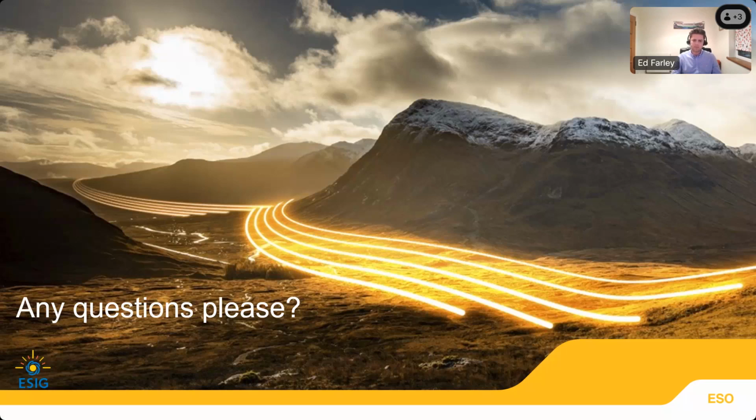How about within GB itself? I think there's some locational procurement of services between north and south, if I'm not mistaken. So for things like short circuit level, where there is a locational element to it, we have specified different regions of need in the Pathfinder process in particular. But for inertia, we currently treat this as a national product, and there's no locational constraints in that at the moment. Although having said that, if further research were to determine that locational inertia could be valuable, then we may seek to reflect that in our market design. Okay.